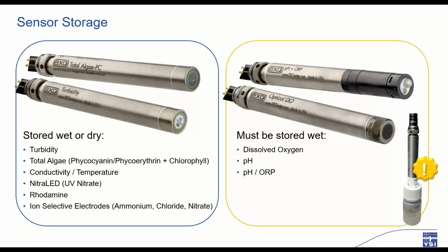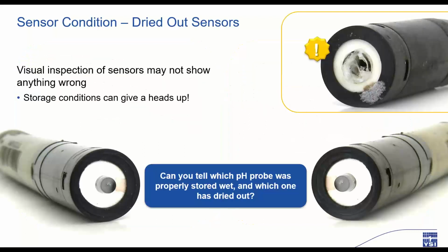The sensors that need the majority of our care are the DO, pH, and pH/ORP sensors. These sensors must be stored moist. So the first step of the new season is to determine if they were indeed kept moist in the off season. How do we determine this? By examining how they were stored. The top picture in this sequence shows a broken pH bulb. There's no sense in trying to do anything with a broken bulb. This is not repairable and is incapable of collecting any valid data. This pH electrode must be replaced.